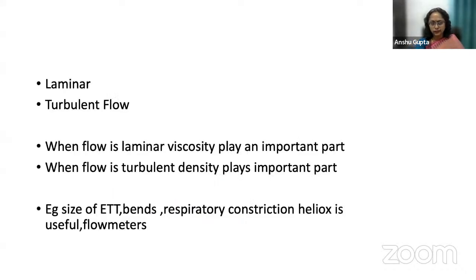Suppose an example of this is we are using an ETT. If its size is not appropriate, the constriction will make it a turbulent flow, and we will not have a good flow. So we have to have a good size ETT. Similarly, bends are not good. They make the flow turbulent.